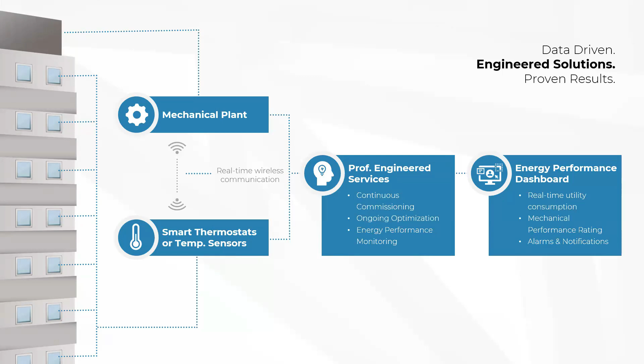But beyond just keeping energy within a band at a high level, all the data is being fed in real time, in terms of, for example, this area is not being heated, or this fan coil looks like it has failed. So Drulo, with this system, is now getting additional alarms and notifications, things that previously would have had to be noticed by somebody and then called in to the property manager, who would call their maintenance team. Now a lot of those issues they're seeing more in real time, and they are even able to fix them before the tenant realizes or before a complaint is lodged.